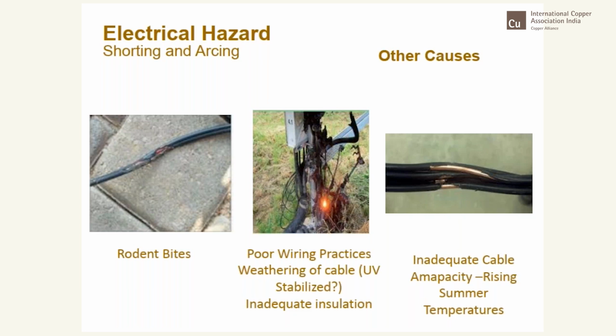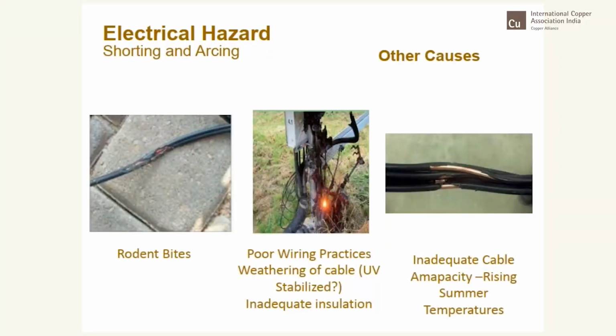And mind you, in summer nowadays, the temperature is rising because of global warming. Not only here, globally, over the last 2-3 years, they said the average temperature is going up year on year. 40 degrees in Spain, 40 degrees in France, you can very well imagine. So when you have a black cable with metal inside, you can see what temperature the conductor would be subjected to. And over and above that, if you have a cable which is underrated, you can understand the disastrous consequences that could follow.